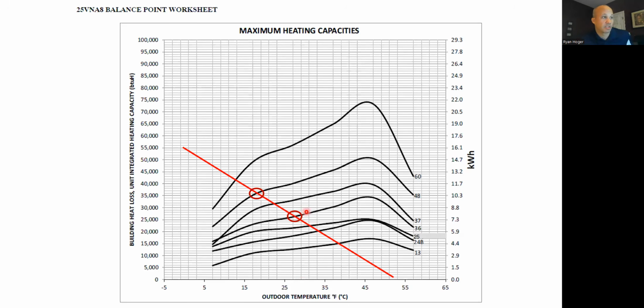So at 27 degrees is when I would switch over from heat pump to fossil fuel. If my electric balance point, my economic balance point, said you could do it at 15, that's great, but I don't have enough heat, so I'm going to have to do it at 27 anyway. But if economically it said to do it at 40, well, at 40, okay, I'll switch it at 40. So whichever one is higher, the thermal balance point, which I'm showing you here, or the economic balance point, on a dual fuel system, meaning any heat that's not electric, fossil fuel basically, I will do it at the higher of the thermal and economic balance point.